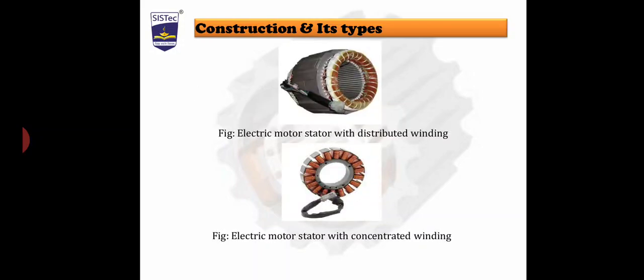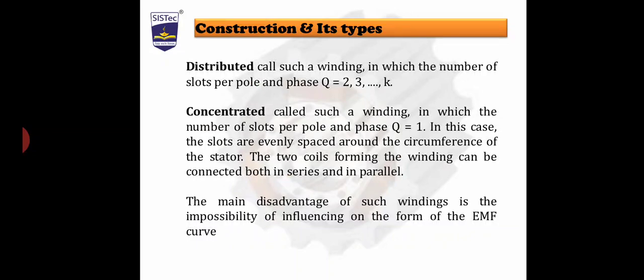This is the stator with the distributed winding — you can see the diagram of the electrical motor stator with the concentrated winding. Distributed winding is defined as winding in which the number of slots per phase, Q, is equal to 2, 3, and so on. Concentrated winding is defined as winding in which the number of slots per phase Q is equal to 1. In this case the slots are evenly spaced around the circumference of the stator.